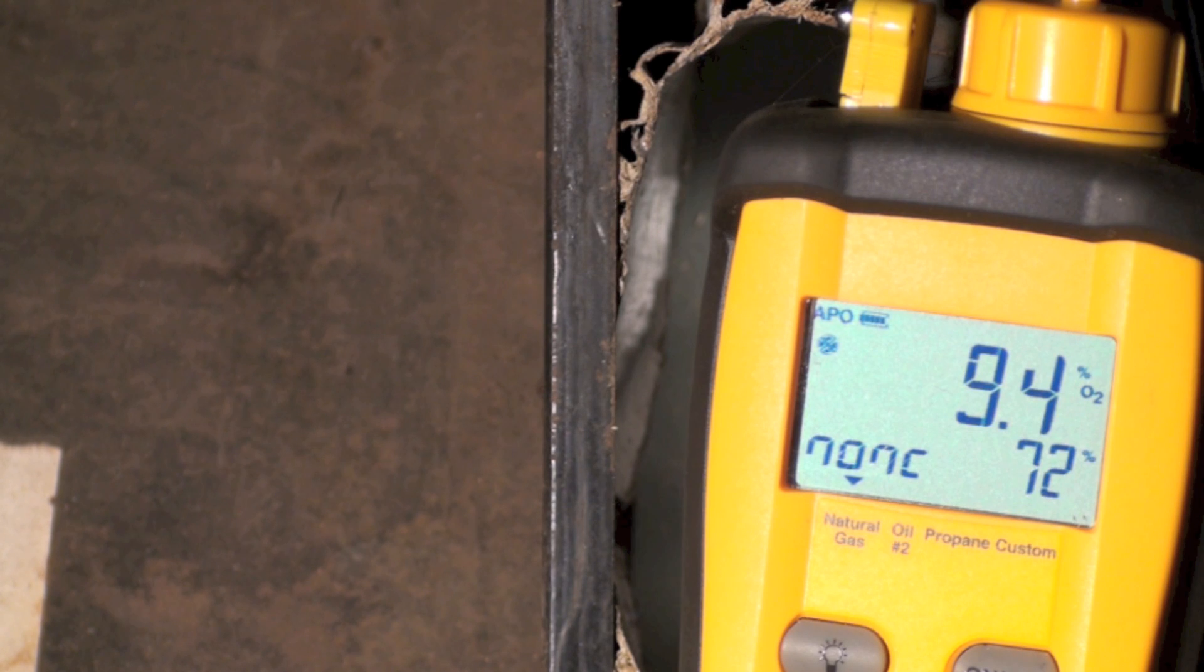So the old practice we used to do of under-firing furnaces really doesn't seem to make much difference. It's pretty much the same. So that's just a little trick on using the combustion analyzer to find out whether I can increase my efficiency of the natural draft gas furnace.